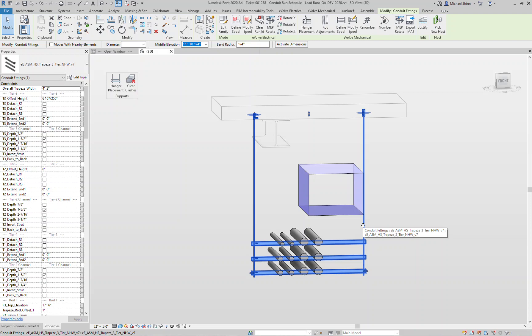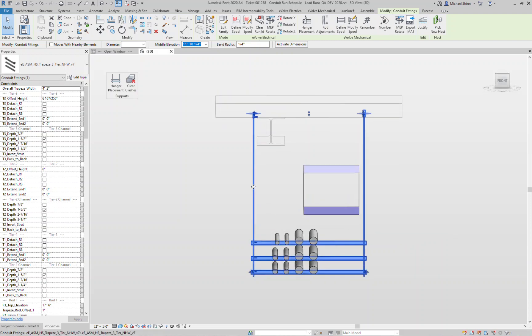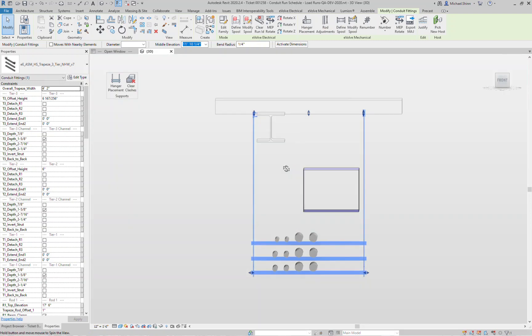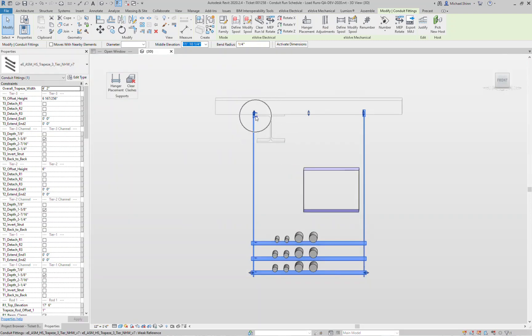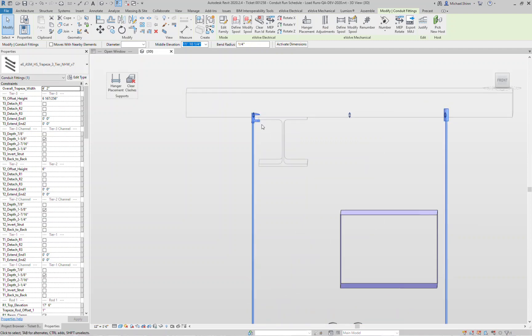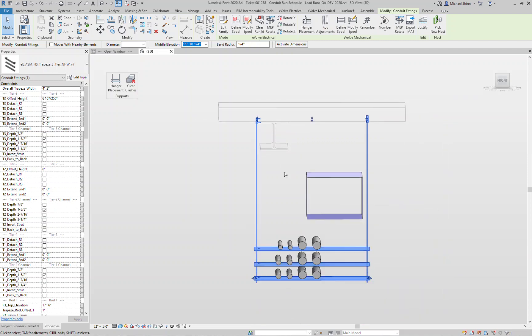And also recognize that this rod here was probably going to hit this beam. It can't move any closer in, so it's going to move it to this edge of the beam and then what is the offset value that applied? So I applied a quarter inch value that I added onto it and it has converted that to a beam clamp. What it's also done at the end is it has applied an overall trapeze width rounding, so it's four foot two, so I rounded to the nearest two inches, so therefore it's now rounded to the nearest two inches.